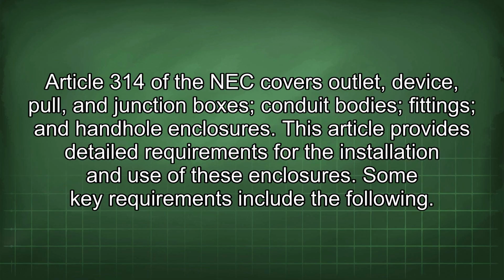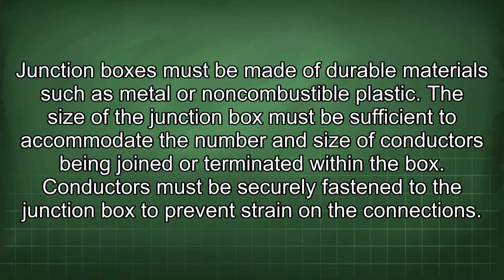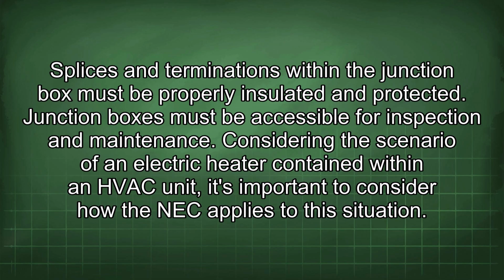Article 314 of the NEC covers outlet, device, pull, and junction boxes, conduit bodies, fittings, and handhole enclosures. This article provides detailed requirements for the installation and use of these enclosures. Some key requirements include the following. Junction boxes must be made of durable materials such as metal or non-combustible plastic. The size of the junction box must be sufficient to accommodate the number and size of conductors being joined or terminated within the box. Conductors must be securely fastened to the junction box to prevent strain on the connections. Splices and terminations within the junction box must be properly insulated and protected. Junction boxes must be accessible for inspection and maintenance.